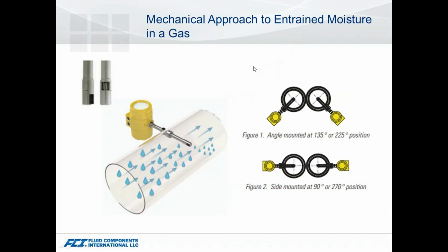For the entrained moisture, for the wet gas sensor, we're still looking at being in that lower half of the pipe. In this case, bottom mounted would probably not be the most recommended because there's some tiny slots in that sensor head, that shroud, to drop the moisture out of it as well.